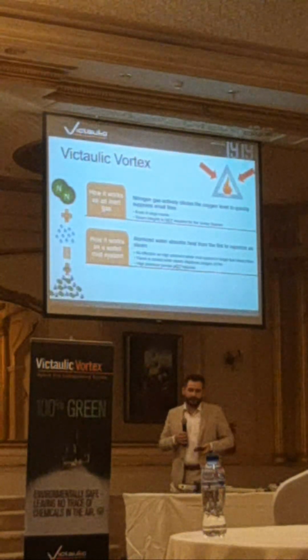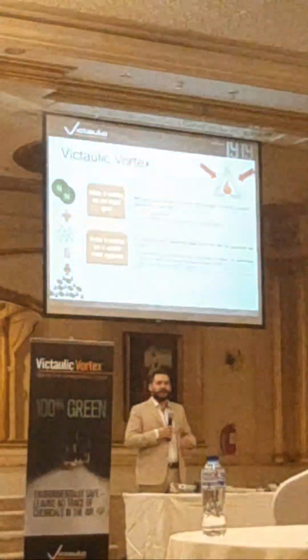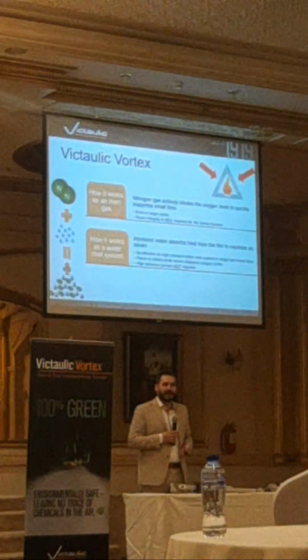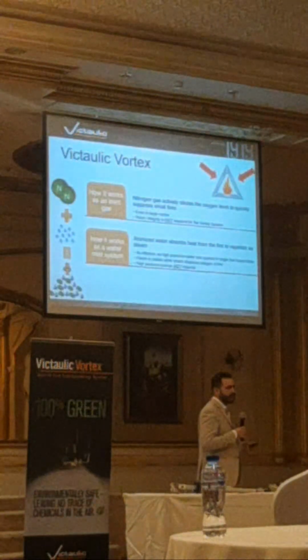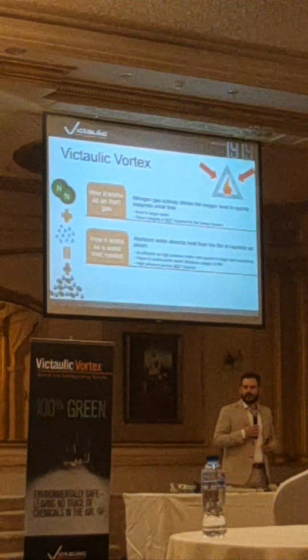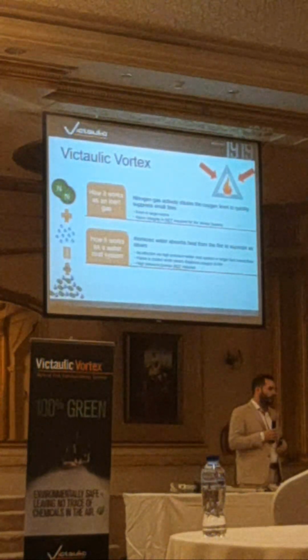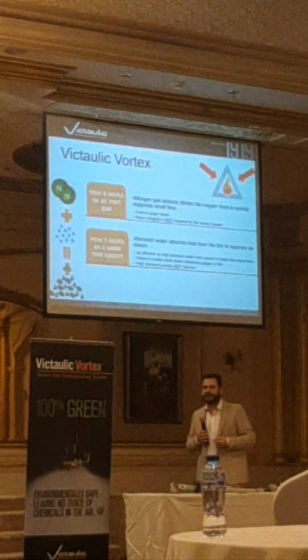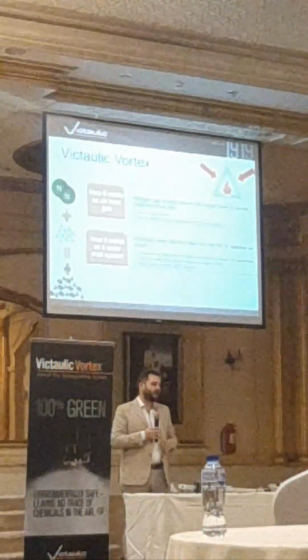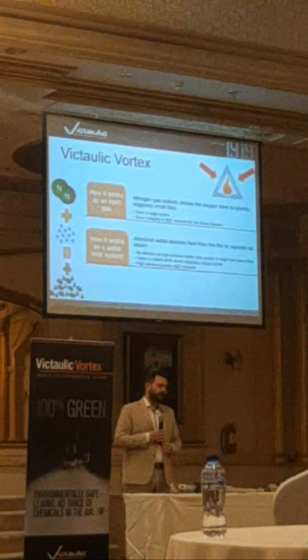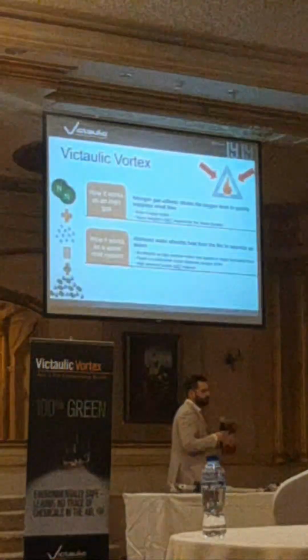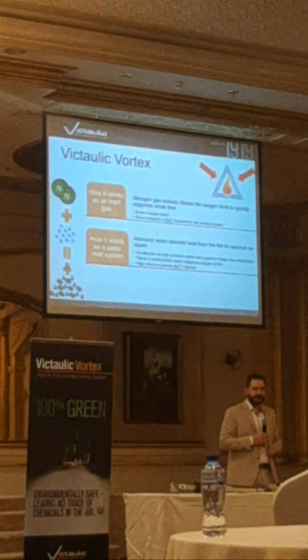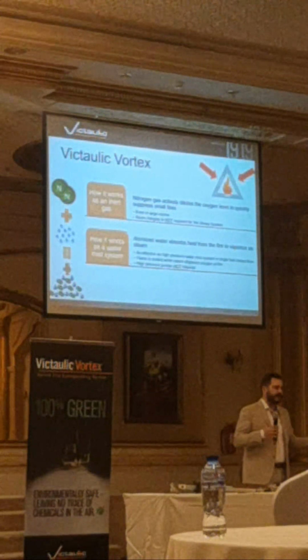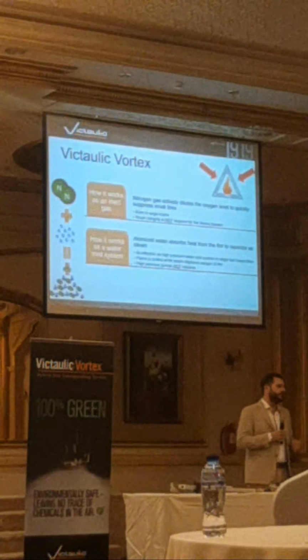When you're looking at a fire triangle, the most basic form of representing a fire, it needs all three legs to continue. You have the fuel itself, and that's not something that you can remove. So what you can attack, however, is the temperature and the oxygen in the room. The temperature we're attacking by adding that very small droplet of water mist. And when I'm saying small droplet, it is going to be 7 times smaller than your average high pressure water mist system. The average droplet size is around 10 micrometer in size. So when you're looking at water mist, it's going to be roughly ranging from 60 maybe to 200 if it's low pressure. But that's the biggest advantage, that we're going to be very efficient in covering the heat of the fire and taking the heat away from the fire.